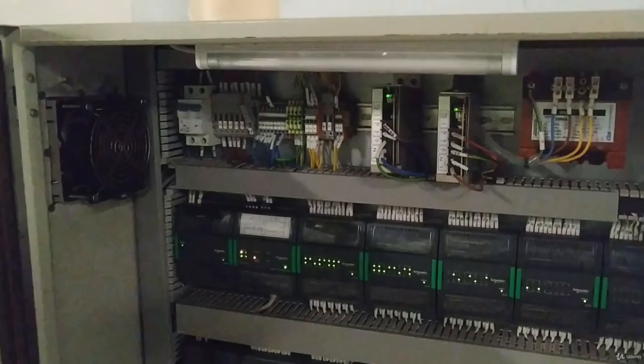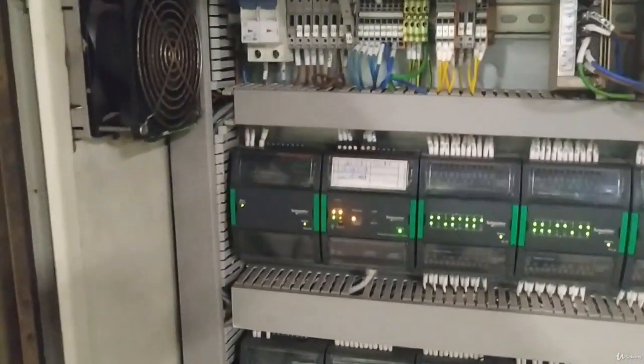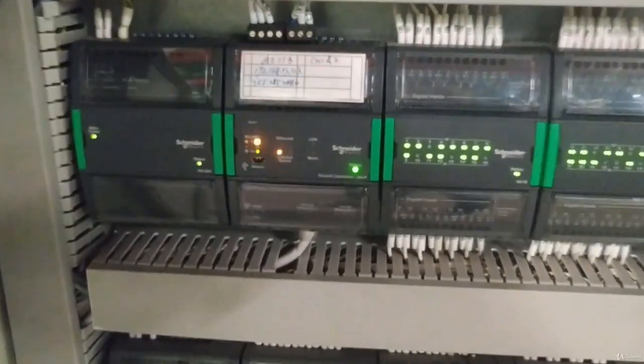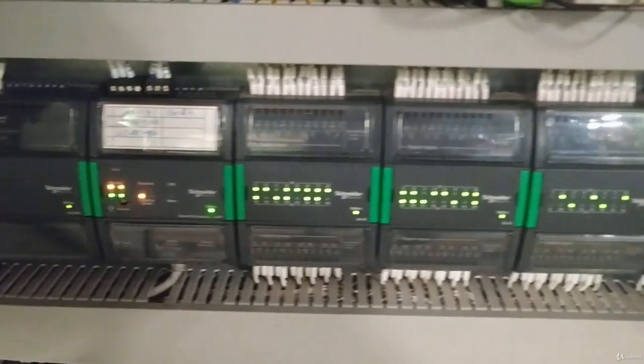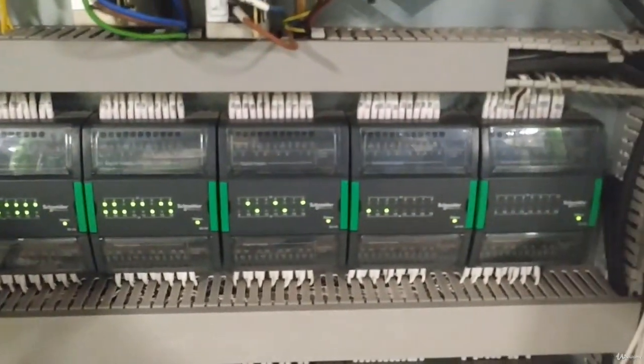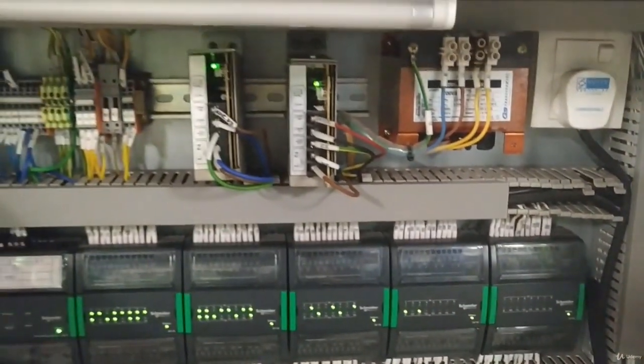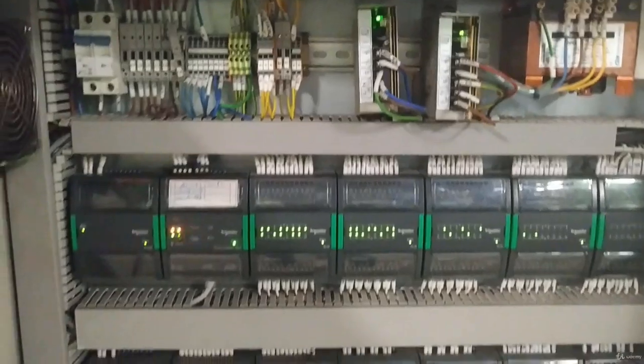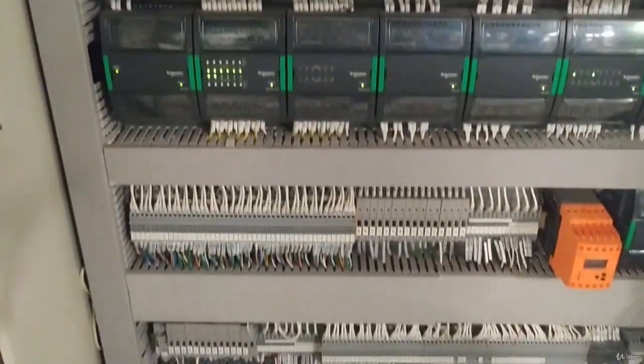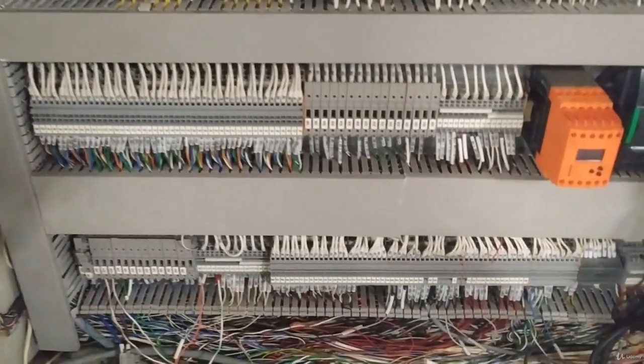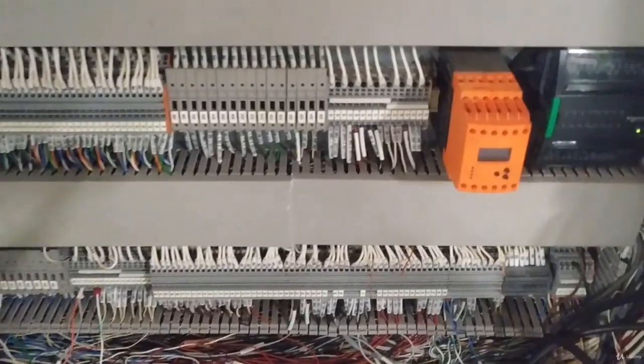And right beside it is the DDC panel that houses the building management system, direct digital controllers and I/O modules. Let's open up the panel and take a look inside. There are many pairs of cables going into these I/O modules, and all these pairs of cables are from the field devices, namely the sensors, actuators, and VSDs of the various equipments.